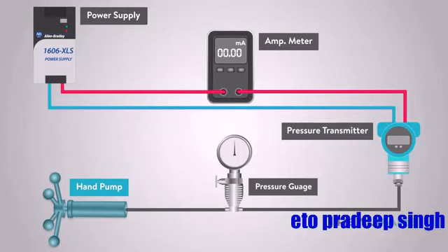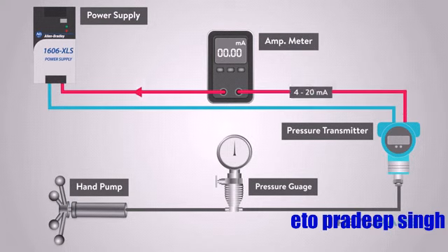Accurate process simulator, in this case a pressure supply, connected to the process side of the transmitter. A current meter is attached to the output to measure the transmitter's 4 to 20 milliamps output. Ideally, a National Institute of Standards and Technology calibrated simulator and current meter are used. In practice, we can use very accurate process meters and pressure input modules.